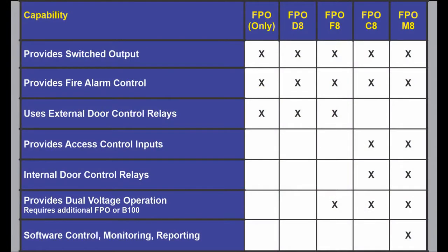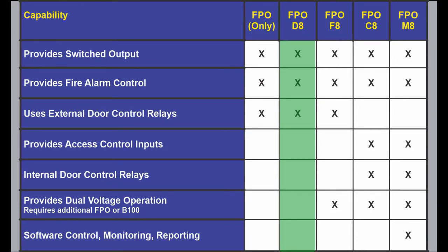The next combination is the FPO D8. This would be used where you have multiple doors and the access system also provides the door control relays. In a typical 16-door system where 14 of them are strikes, two of them are mag locks, all are 24 volts, I would use an FPO with two D8s.